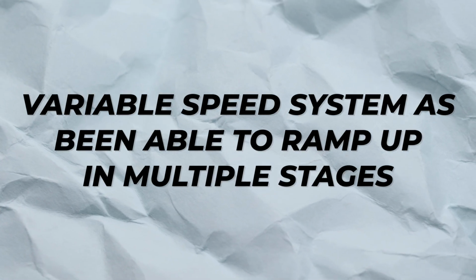A variable speed system, unlike a single stage system which is either on or off, can ramp up in multiple stages. The compressor can run at multiple speeds, running at 20% capacity, then 30, then 40, then 50.